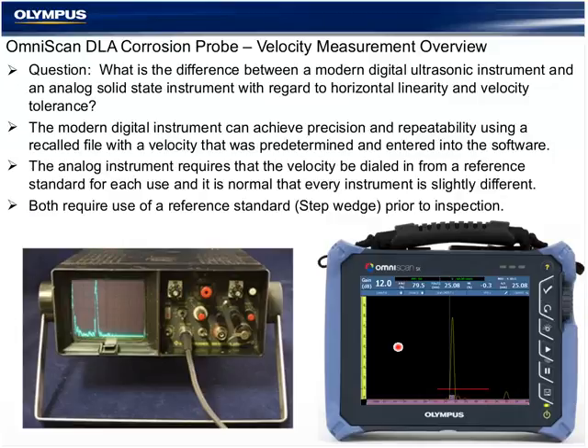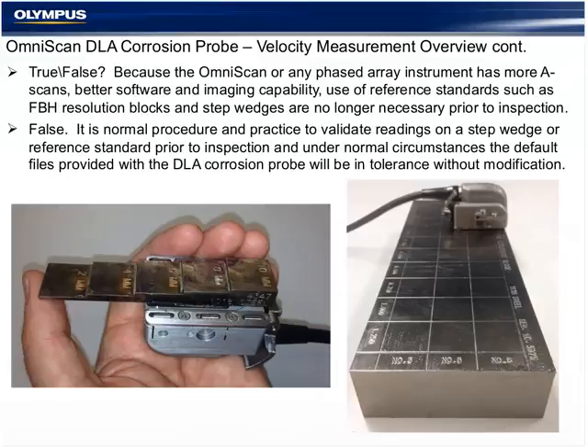And we see this a lot in both weld inspection and in carbon steel when Olympus support is often asked to troubleshoot data or repeatability problems. It normally comes back to a velocity error. So both of these would require use of a reference standard or step wedge. But again, entering the velocity and validating the reading is much preferable than a coarse velocity measurement where every inspector is using a slightly different velocity.